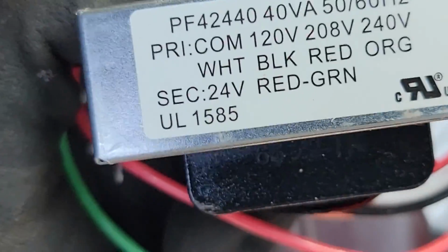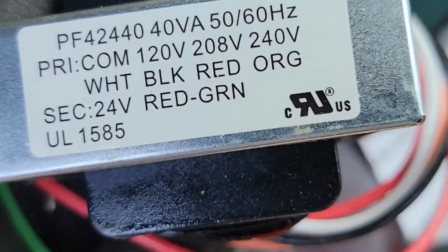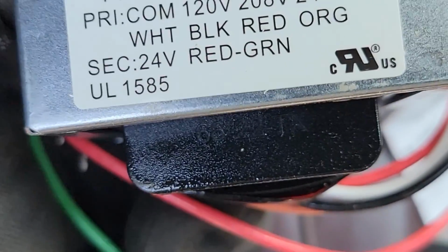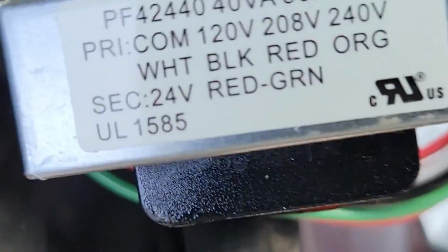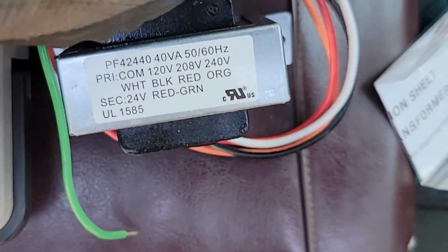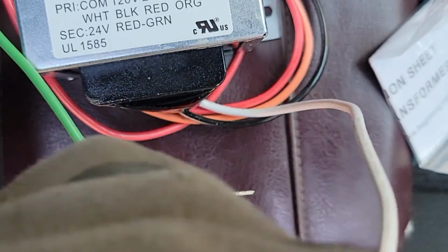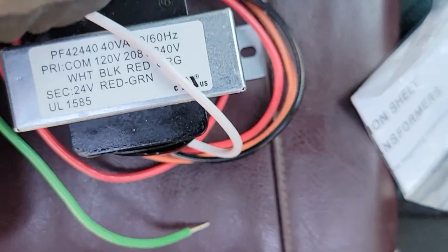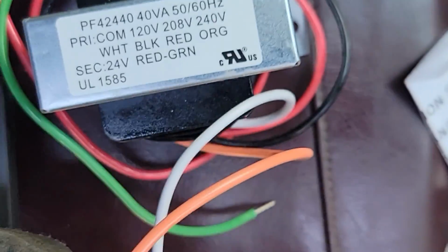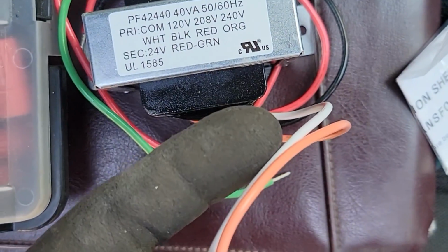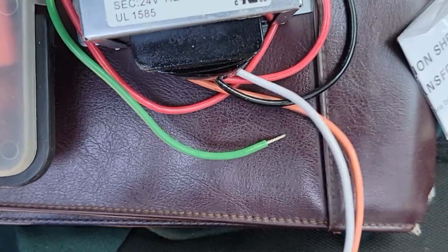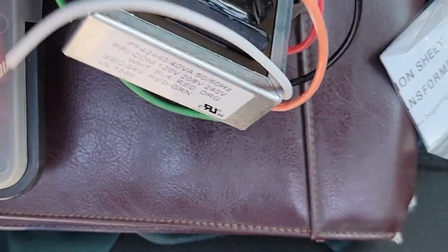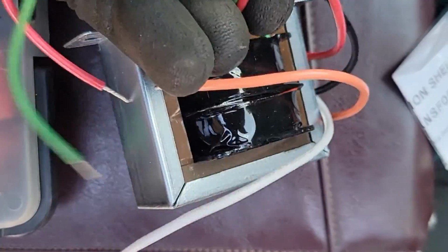Here's my new transformer, and you can see that I'm going to be using, since this is 230 volt, I won't use the black or the red wire. I'll use the white and the orange wire, and then my secondary is the red and green. So I will be using this white wire here and this orange wire since it's 230 volt. Okay, so this will be my primary coming into the transformer here. Okay, and then this right here, these two wires on the other side will be my secondary.